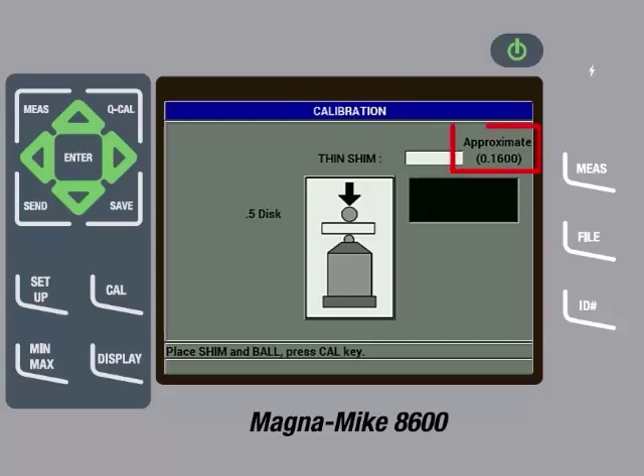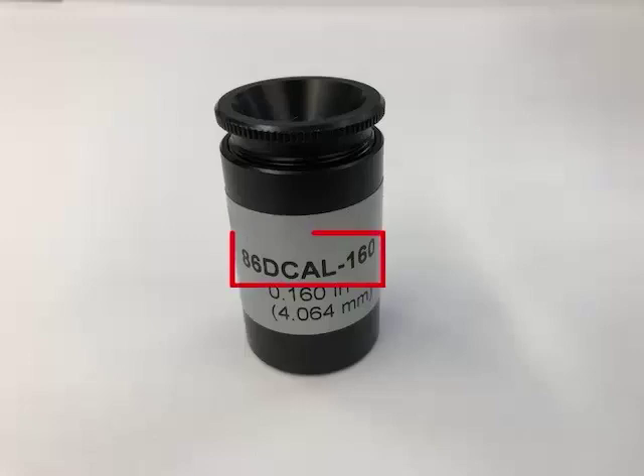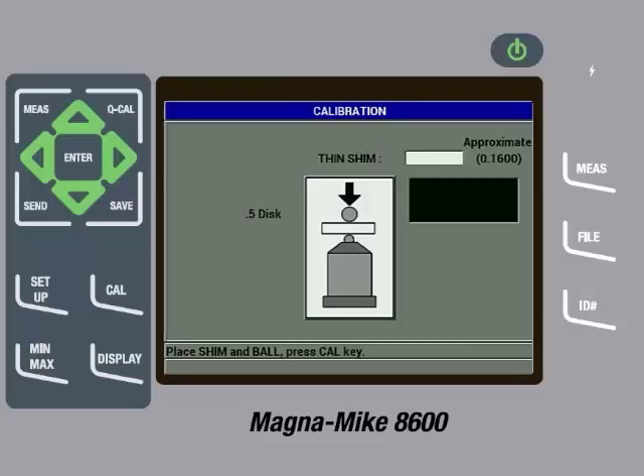The gauge will then ask for a thin shim and call out an approximate thickness. The thin shim called out for the disc target being used is 0.1600, or if you are using metric units, it would be 4.064. The English units of the approximate thickness being called out for the thin shim corresponds to a part number in the calibration kit. So the next step is to find the 86D Cal-160 reference standard. The reference standard includes a shim made of either brass or aluminum that is a particular thickness. The actual thickness of the shim is printed on the reference standard in English and metric units. It is very important to enter the actual thickness of the shim and not the approximate thickness that is being called out by the instrument. In this case, the thickness printed is actually the same as what is being called out by the gauge. But this will not always be the case.